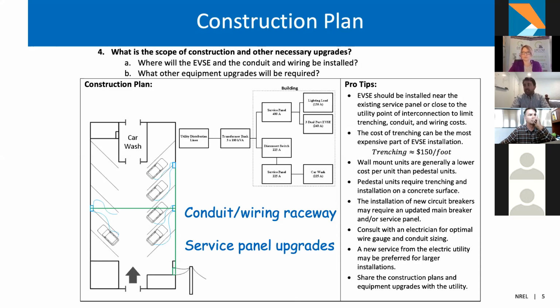That's where we decided to upgrade the service panel to a 400 amp service panel, then feed each of those sub panels a separate lighting load, maintain the current panel at 150 amps, and install an EVSE panel at 240 amps for all the EVSE.